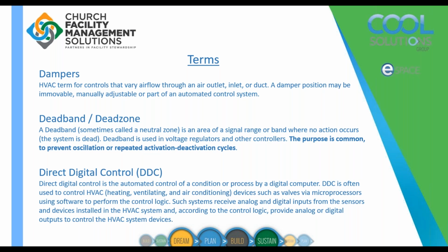Deadband or dead zone. This is something that I see a lot and we talk about a lot. I've highlighted a certain section of it. You see the bolded section. The purpose is common to prevent oscillation or repeated activation, deactivation cycles. So when we're talking about deadband, typically your heating set point and your cooling set point, that creates a deadband, the distance between those two set points. The farther they are, it creates a greater opportunity for your equipment not to be energized. It's a fancy way of saying you can save money if you have a larger deadband.